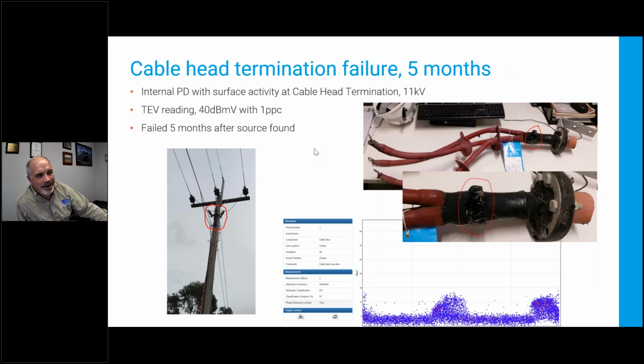Very briefly, hit you with it there. Here, looking from the ground with TEV, we basically put TEV on the ground strap from these points, and we could see a phase resolved plot as a result of bad termination on this cable riser. And so it was internal. We couldn't pick it up with ultrasonic. But, well, no, I'm sorry, I'm lying to you. This is an ultrasonic plot with the dish, and it's finding PD. The algorithm says it's PD, and the phase resolved plot looks like it's PD.